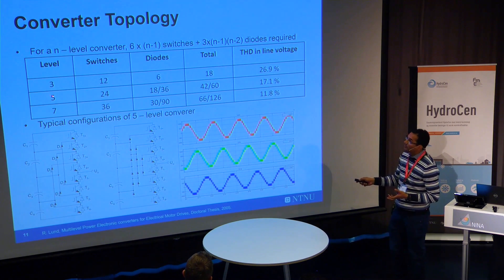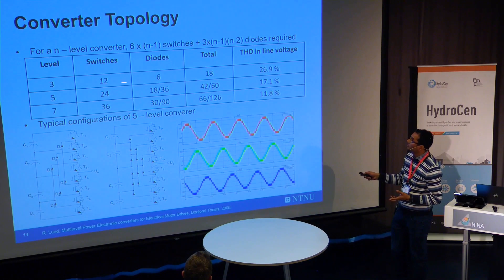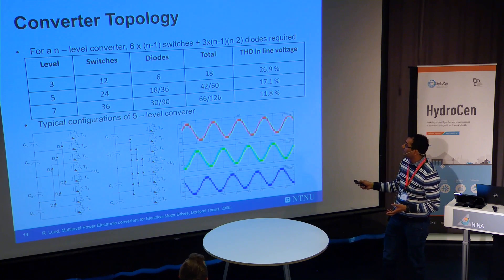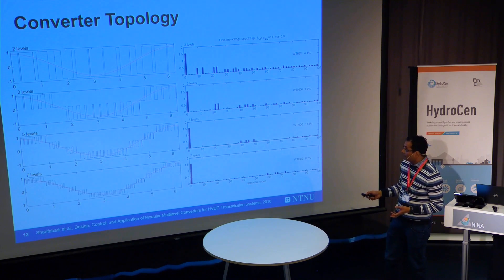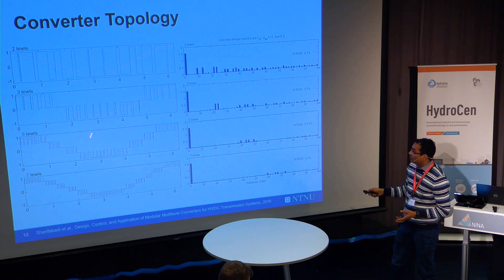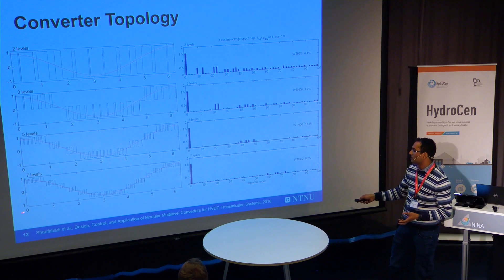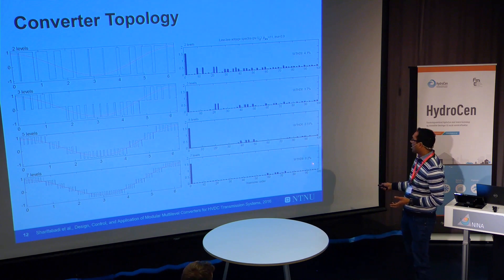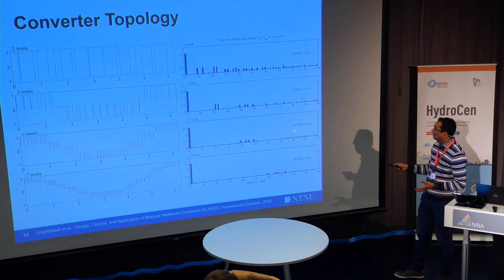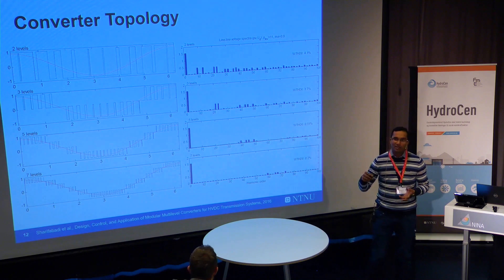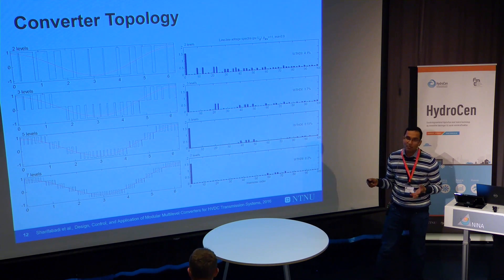As we go from three to five to seven levels, the harmonics decrease significantly. At seven levels the output is almost sinusoidal — about 0.2% current THD. At five levels we have 0.5% current THD. As we go higher in level, we have less damper-winding loss in the machine, but the system becomes more and more complex with more and more switches required.